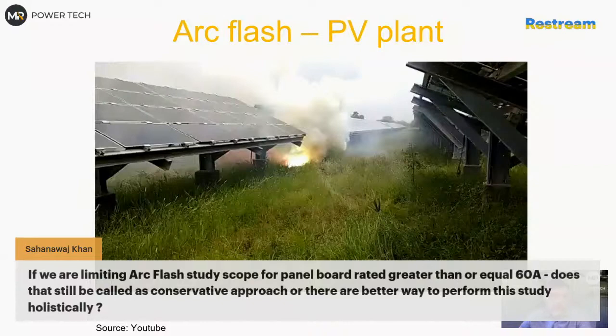Typically below 63 amp it is unlikely in normal AC systems to have energy above 1.2 calories per square centimeter because of the protection. Because if you don't have a protection, of course, it's different. But if you have a protection like a 63 amp MCB or fuse, it will be below 1.2 most of the time. You might just have to be careful on DK characteristic MCBs. But this is my first approach as well.